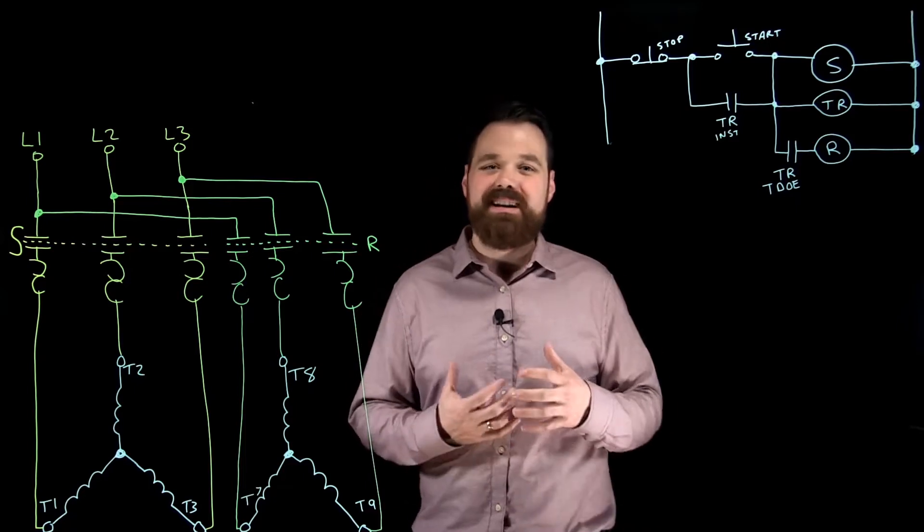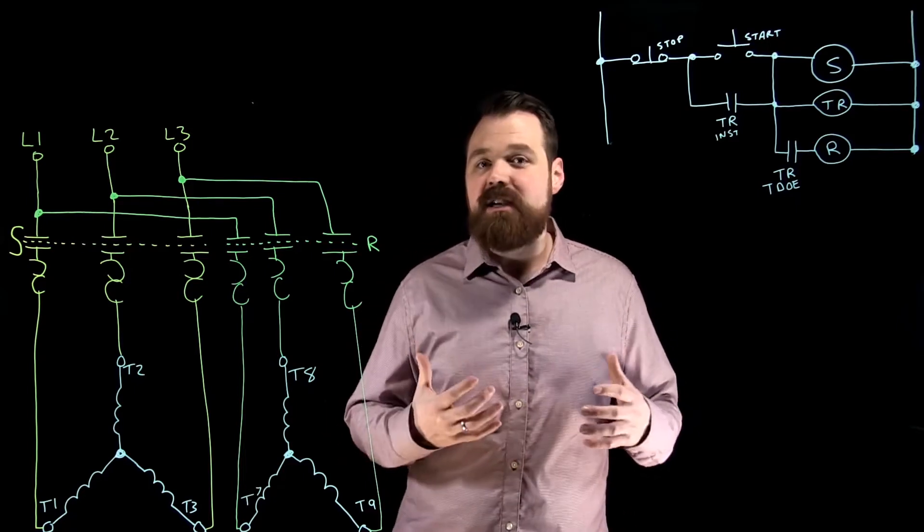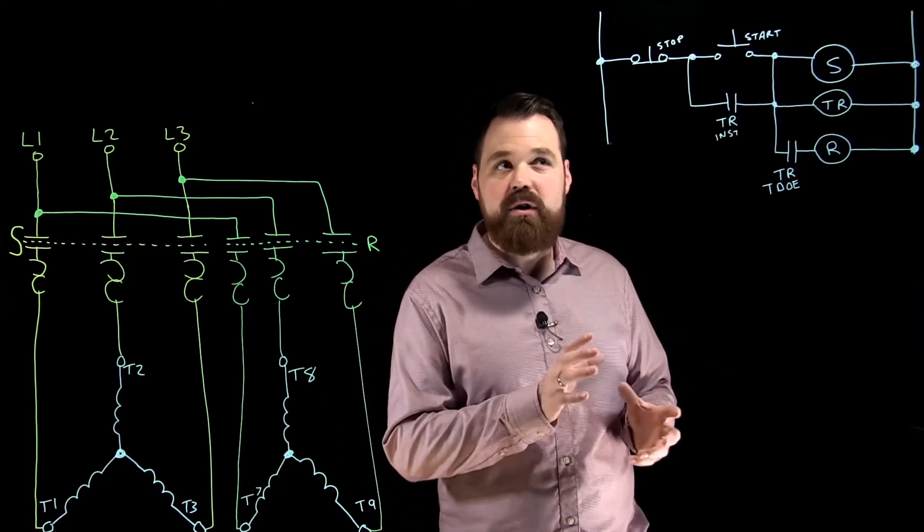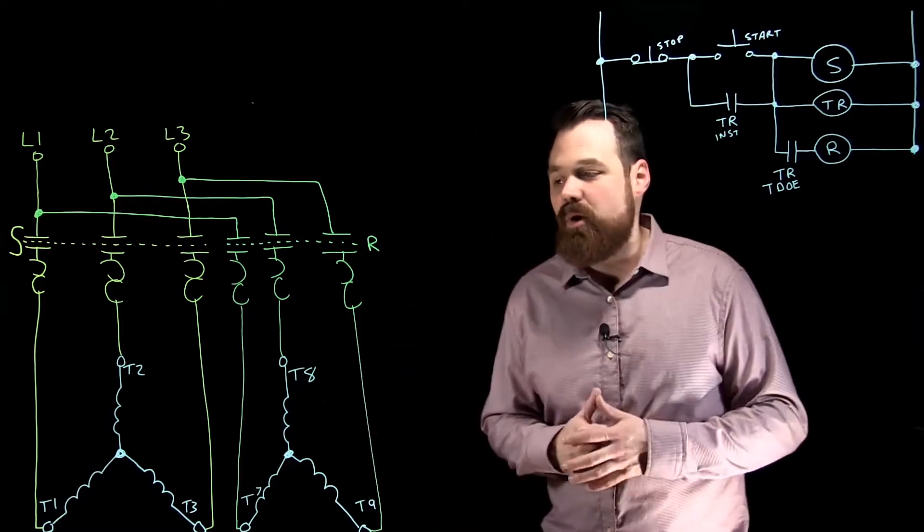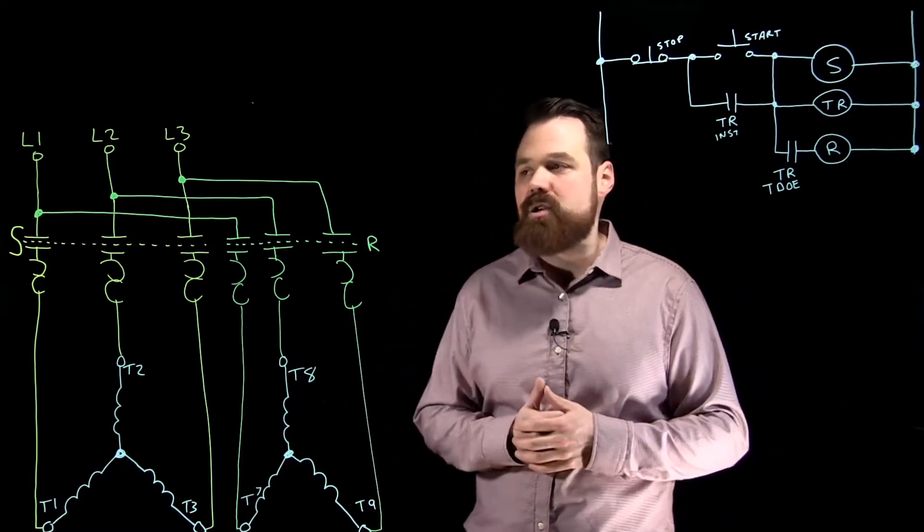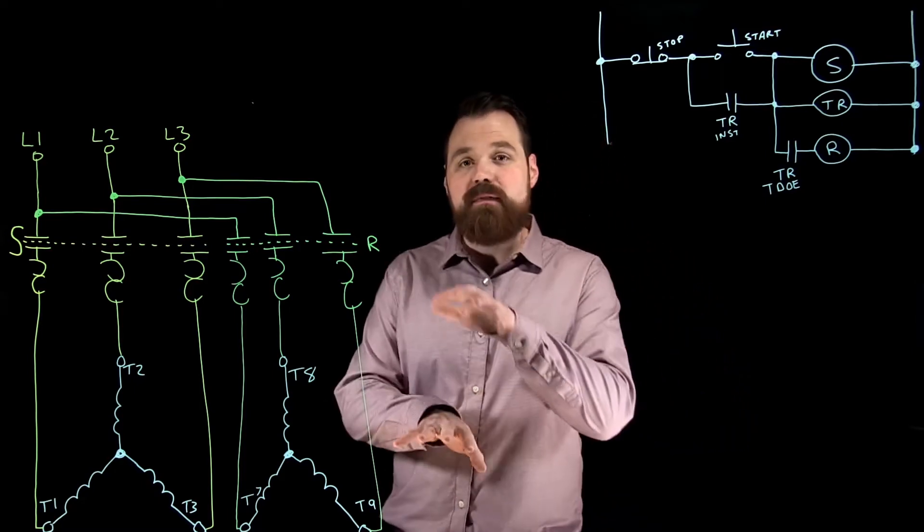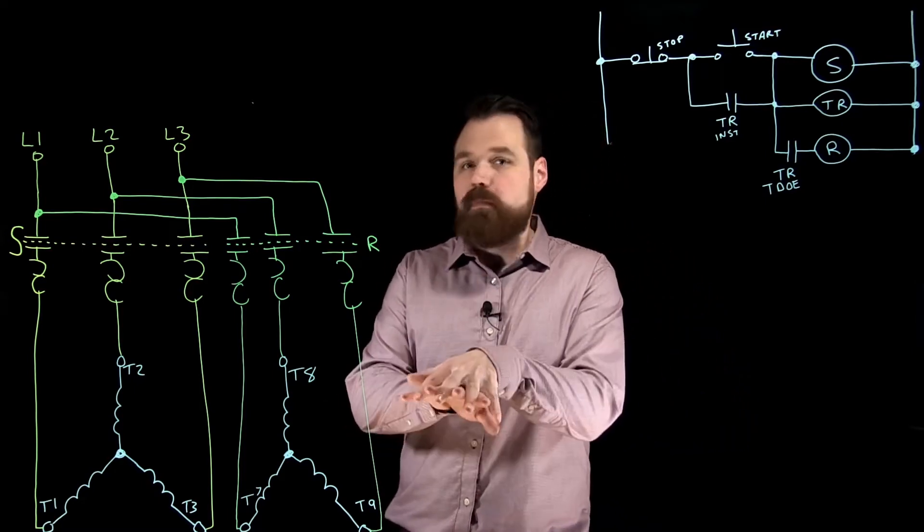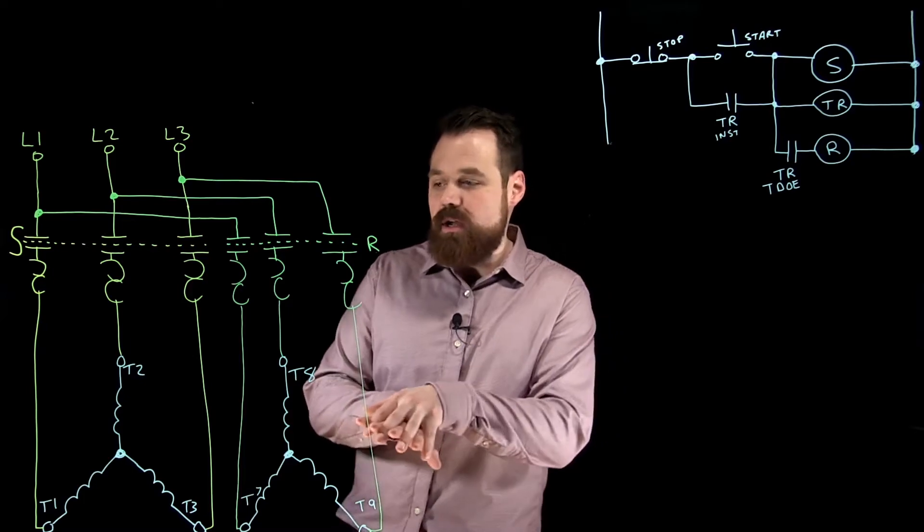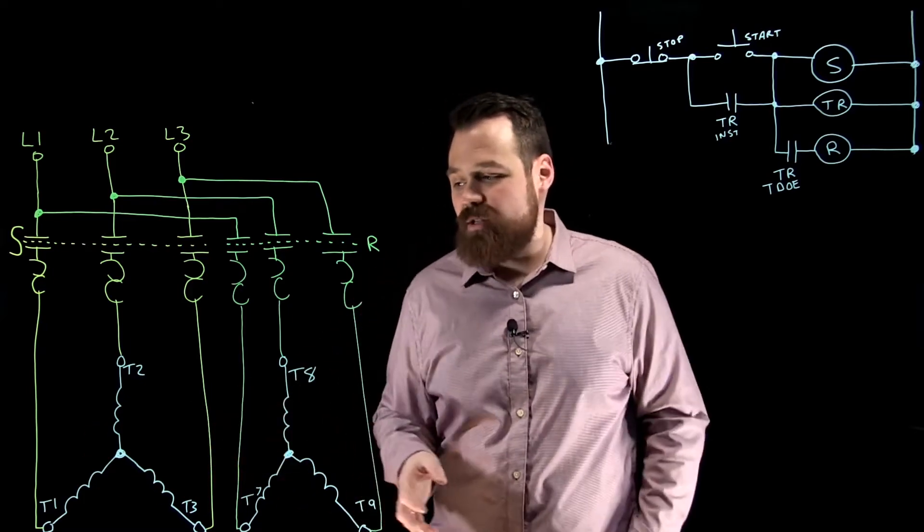So with this part winding starter, it is a specific type of motor, so you want to ensure that your motor can do part winding starting. Essentially how it works is the motor has two different windings in parallel on top of each other, usually in this Y formation like this.